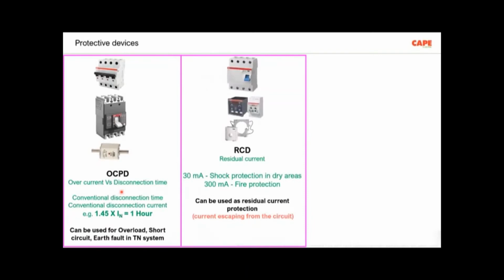Here, what you should understand is the disconnection current. The maximum allowed disconnection current is 30 milliampere. That means for a leakage of more than 30 milliampere, the device RCD is supposed to trip. 30 milliampere is the shock protection in dry areas. This is the maximum allowed current for shock protection. That means if you want protection from electric shock, you must use an RCCB of not more than 30 milliampere.